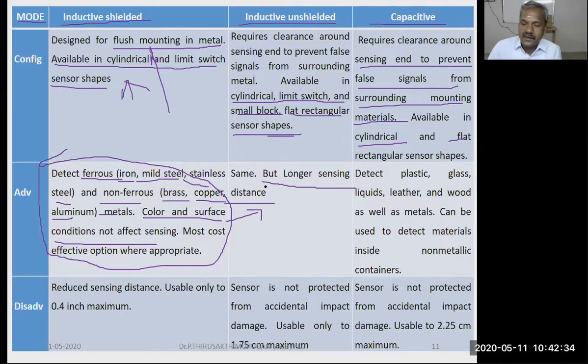Not only is it longer, the unshielded proximity pickup also detects side objects, because of its side sensitivity. Objects approaching from the sides of the sensor probe are detected, whereas the shielded type detects only objects directly in front. The shielded type can detect small objects, whereas the unshielded detects large-sized objects.